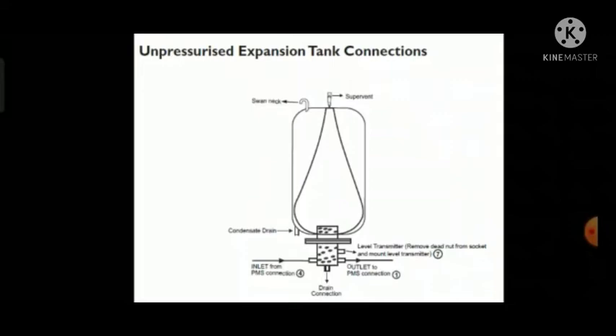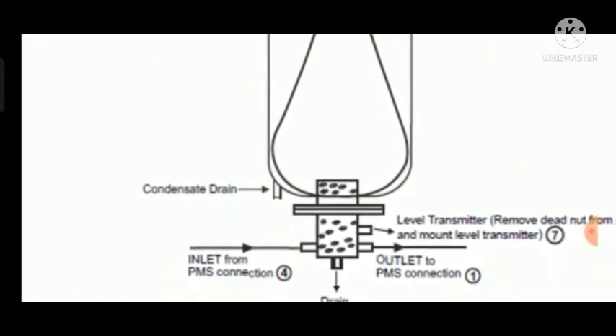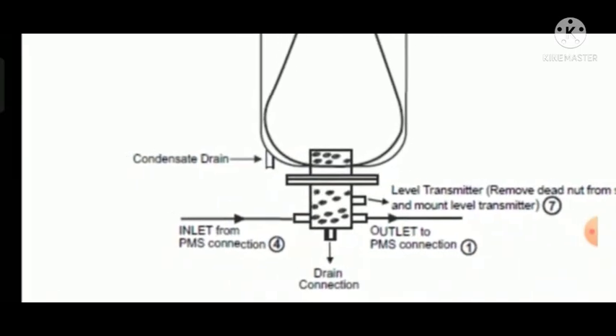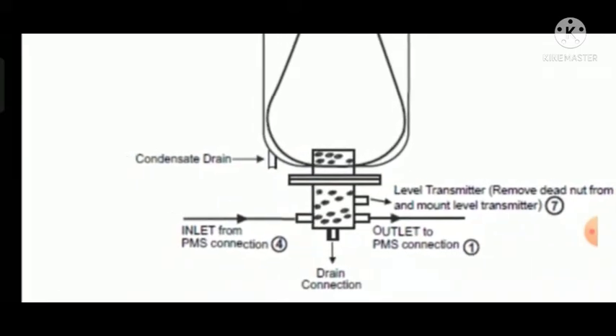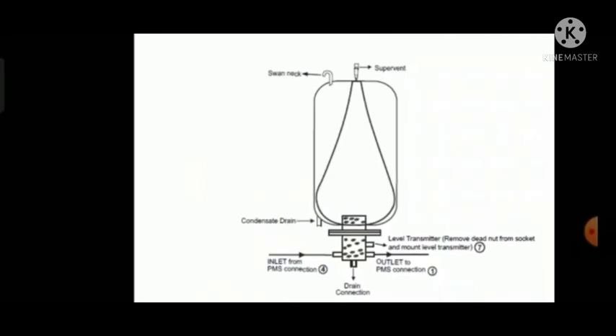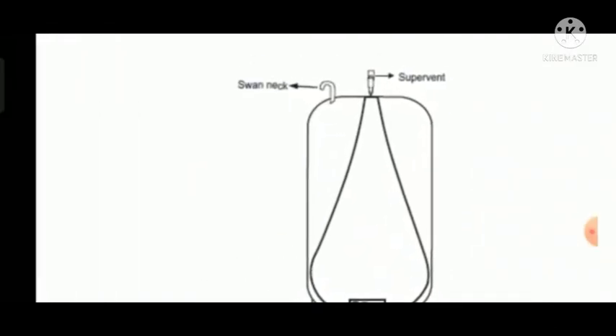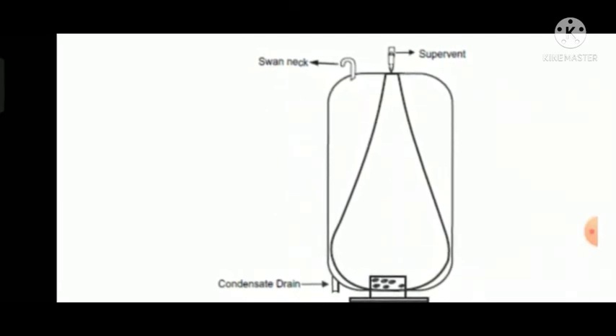See here, this is the unpressurized tank. If you see here, the inlet and outlet are on the same line. So from one side the inlet is coming from that pump, and this outlet is again going back to that pump, as numbered, serial numbers 1, 2, 3, 4, 5, you can see. And one more thing here is a level transmitter. The level transmitter is supplied along with the pumping set, and it is wired and packed nicely. So at the time of commissioning we have to connect this level transmitter to the point marked here. And this super vent and swan neck are also loosely supplied, and you have to install them at site. This is part of our supply, and you just need to install it at the site.